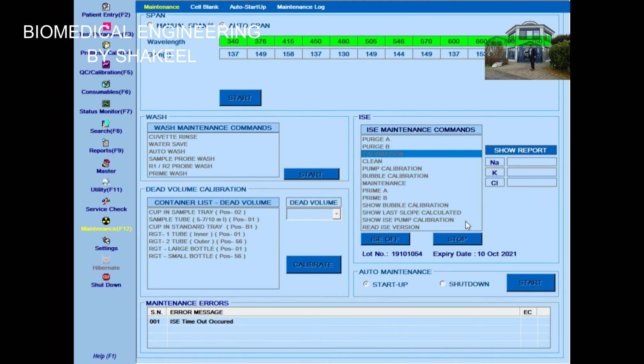So let's start. So this calibration which is for sodium, potassium and chloride, and the value of sodium is from 52 to 64, potassium also from 52 to 64, and chloride from 40 to 55. So we will see what our results will be. If our results are within this range, then the color will be green. If it is out, then it will be red in color. So just wait for the results. It won't take a long time. Okay, so let's see it. You can see that it is green color and all are within the range, which means our calibration is passed.